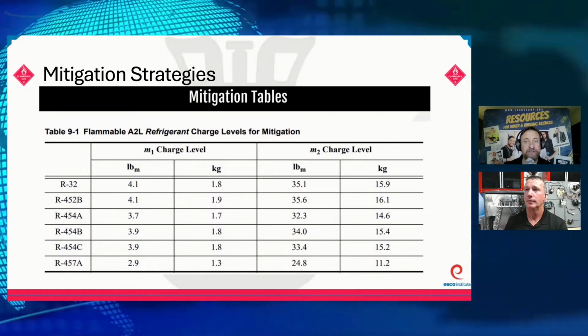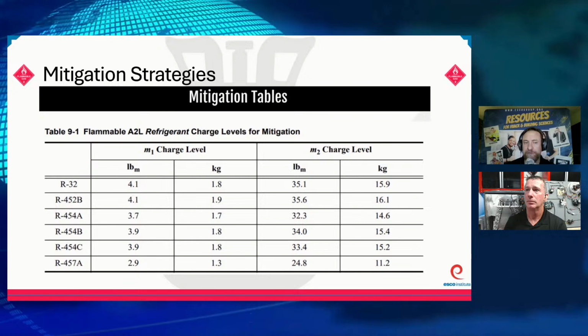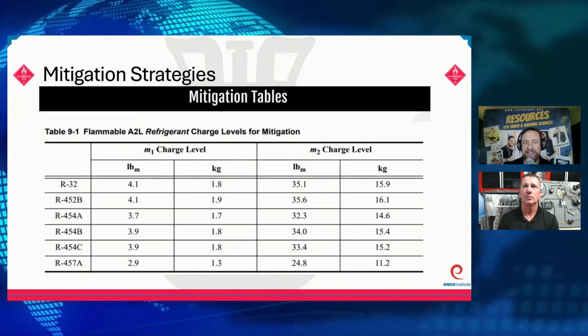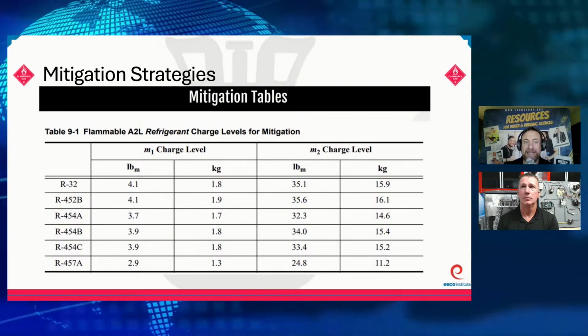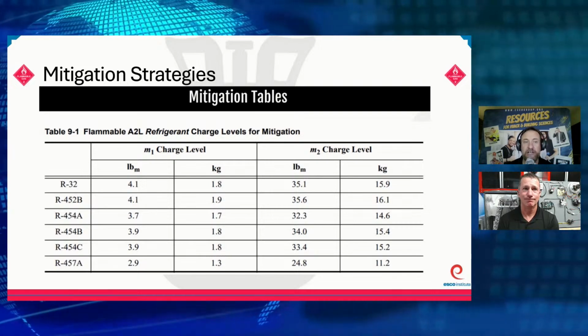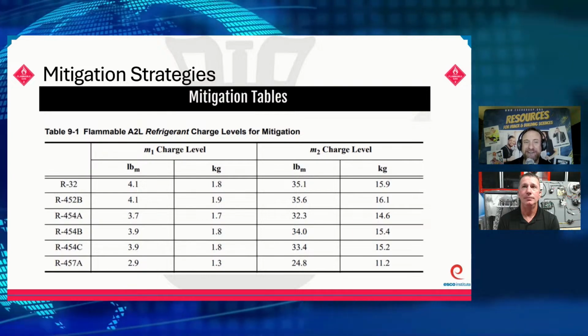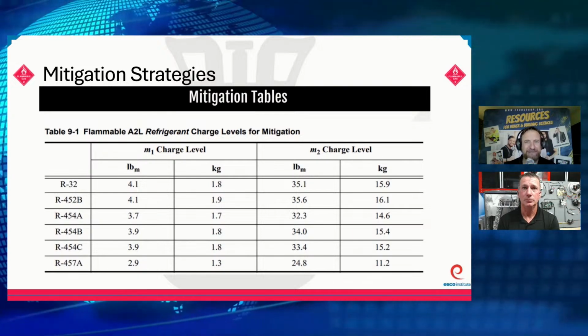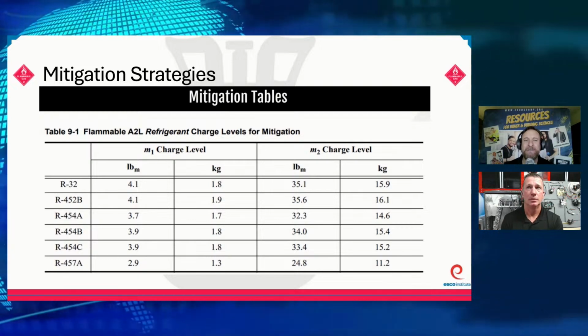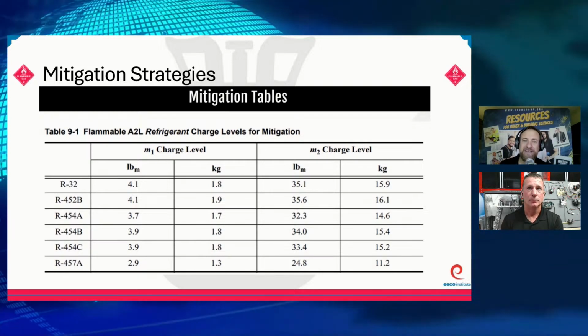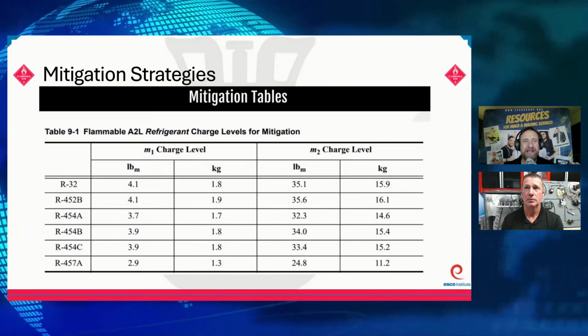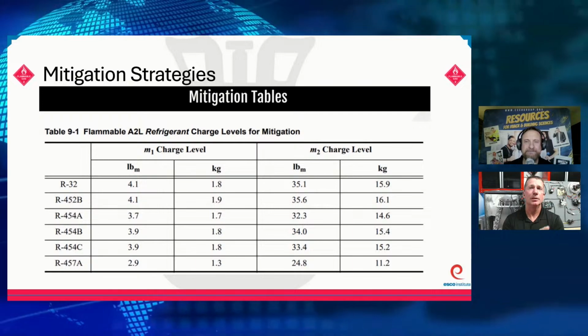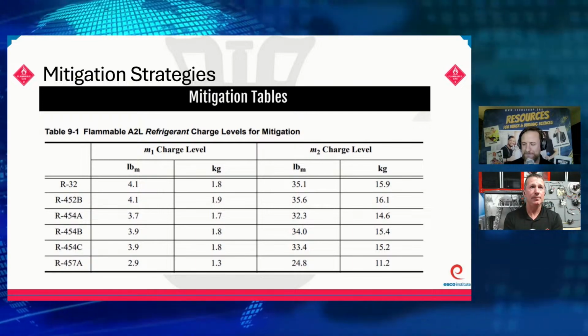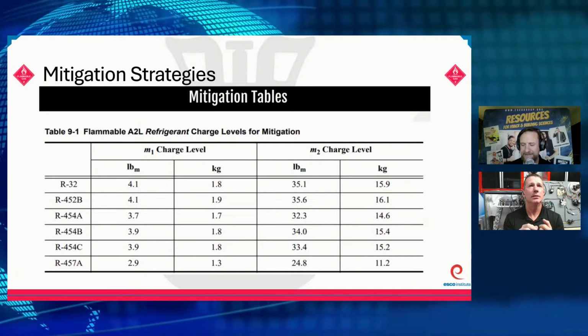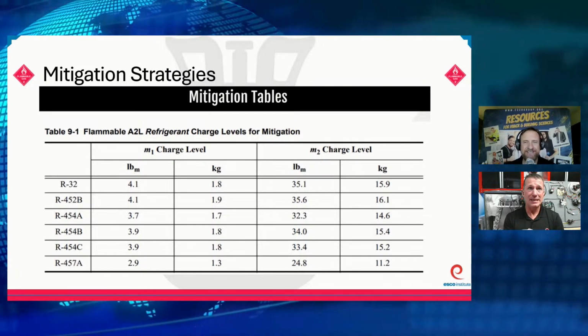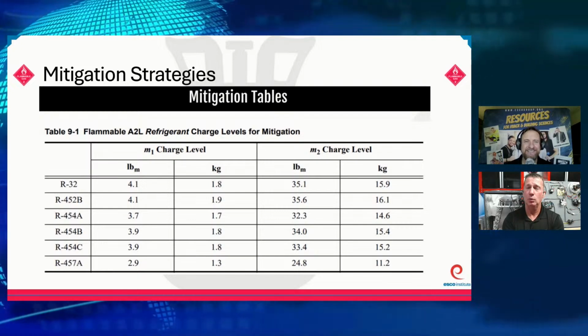But also, we have to take a look at that. It's very important for us to look at those installation manuals because some equipment with 454B has the same exact 3/8 line. Other equipment with 454B may have a 5/16, 1/4-inch, or the 3/8 line, and the flex line can be different also. We've always supposed to have been reading that manual for oil return alone, but now we're going to be looking at that liquid line a little bit more than we have in the past. And I'm not an engineer, but I imagine that this table has a lot to do with that. Yeah, absolutely. So what we can anticipate to see is our ductless mini splits, our window shakers, and our PTACs not having any mitigation whatsoever.